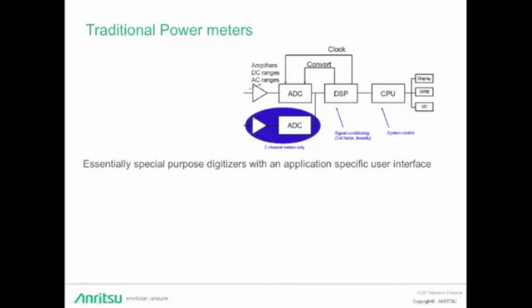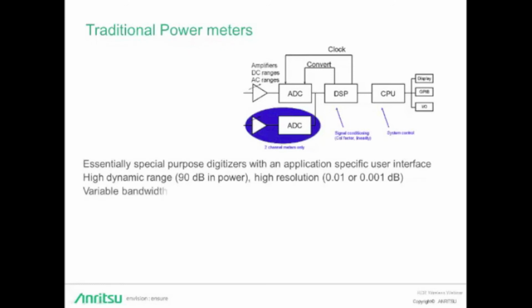So power meters are essentially special purpose DC digitizers with an application-specific user interface. They have high dynamic range and high resolution demands, which require gain ranging in front of the ADC. As signal levels get low, the reduced signal to noise ratio often requires a reduction in bandwidth for meaningful measurements. The low sensor output voltages at low powers require very careful attention to DC error sources in the amplifier.